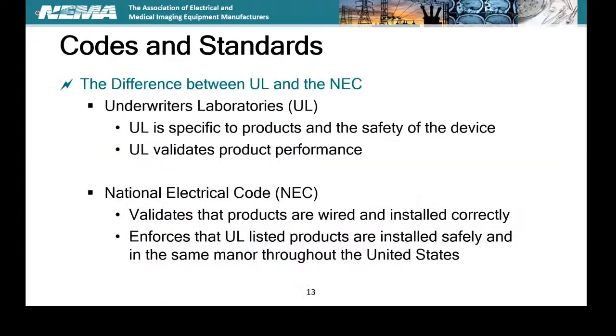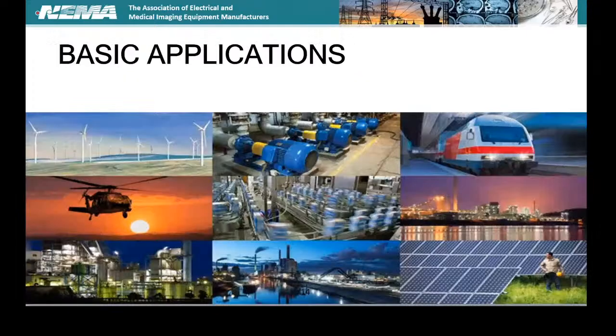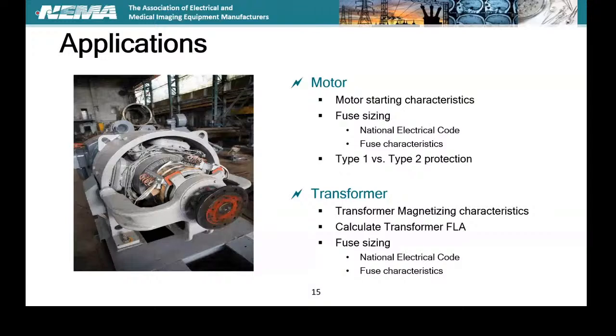All right, so I'm going to skip this one and go right into basic applications. The first one we're going to look at is motors, because motors have unique starting characteristics. We have general rules in Article 430 on fuse sizing, and they pretty much call out the different characteristics of fuses and circuit breakers. We're going to talk a little about what Type 1 and Type 2 protection is for motors and motor controls. Then we'll talk about transformers and the characteristics of inrush current, calculating full load amps, and then fuse sizing based on the rules, whether it's primary or secondary, and we've got some examples.